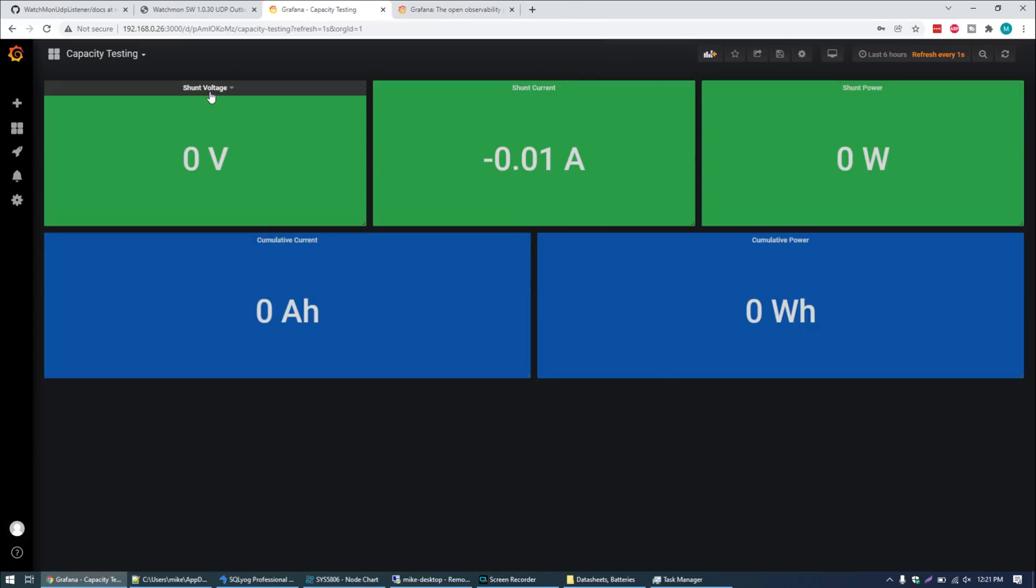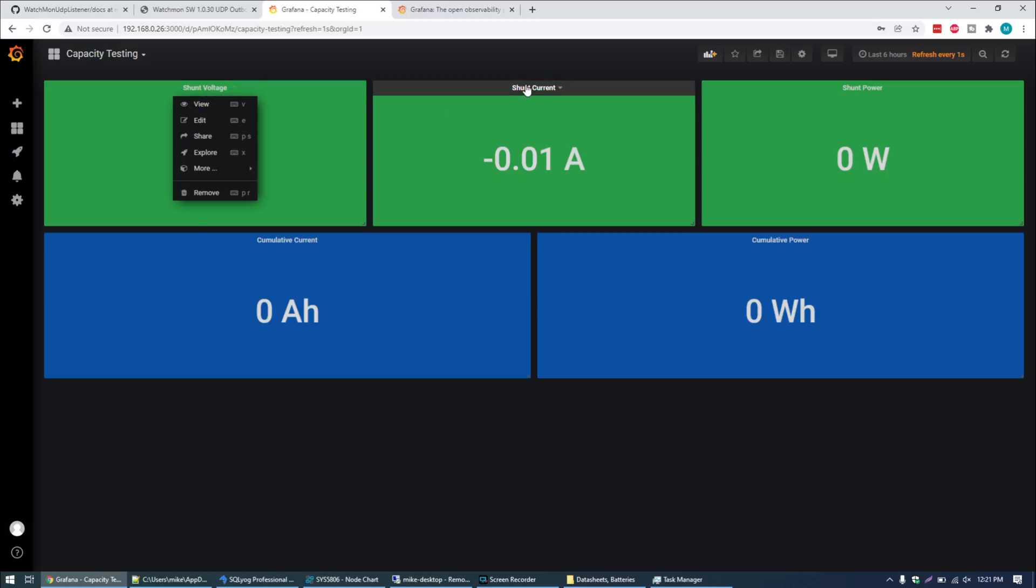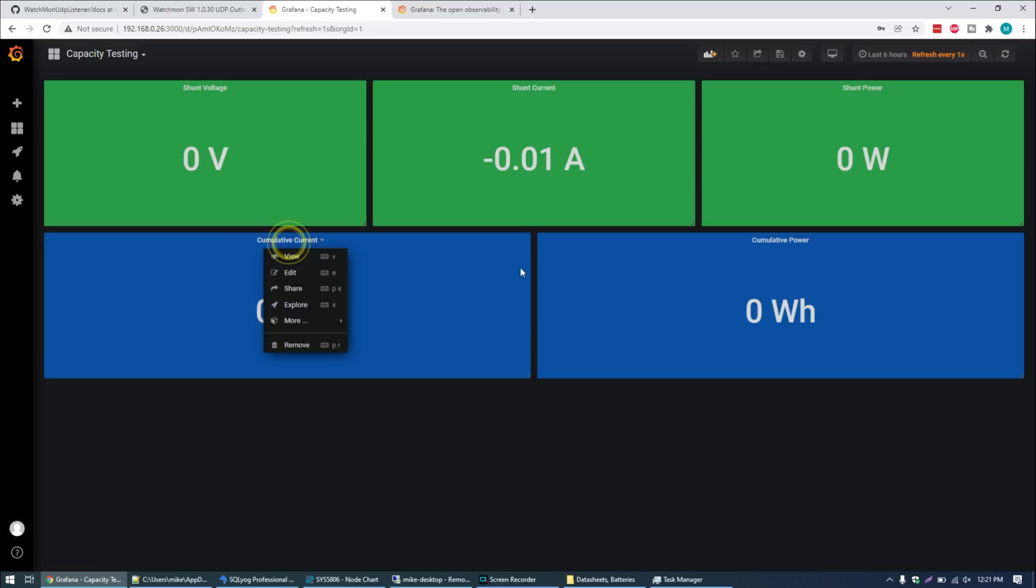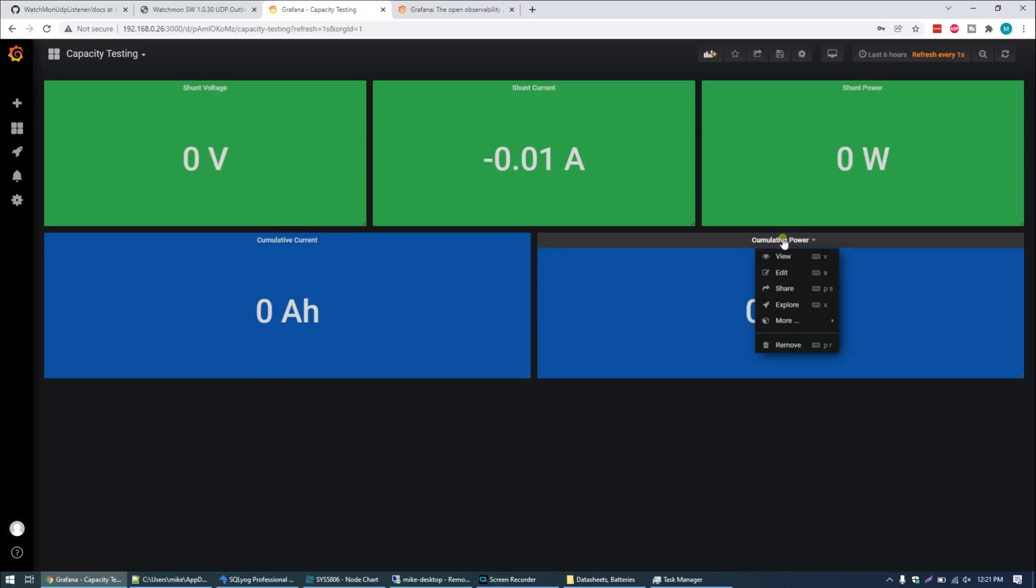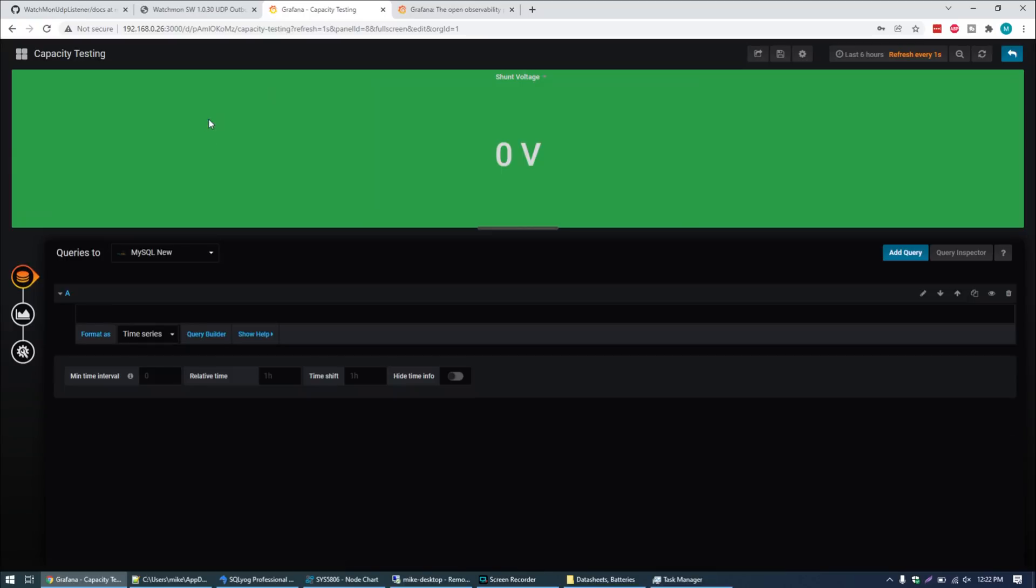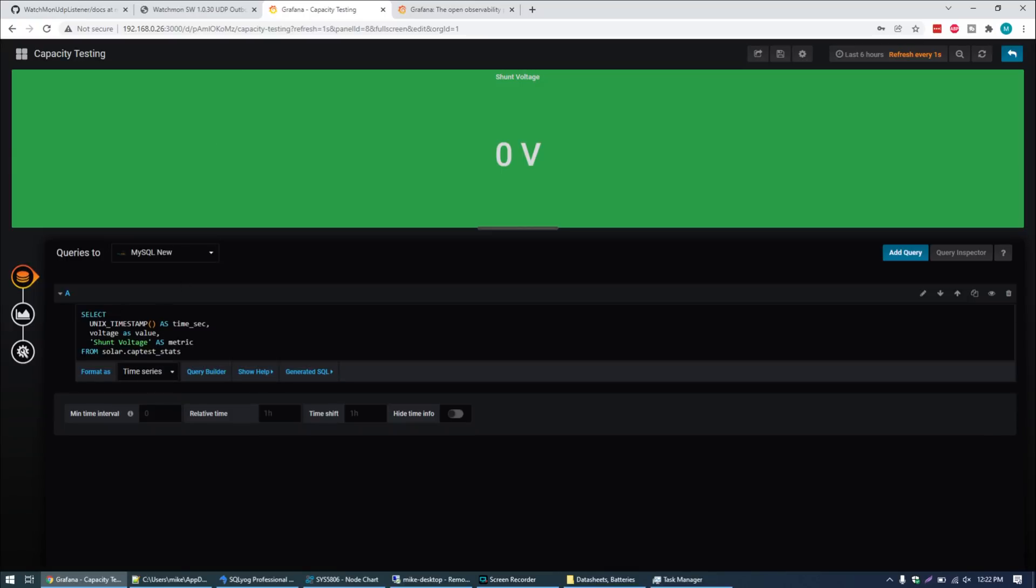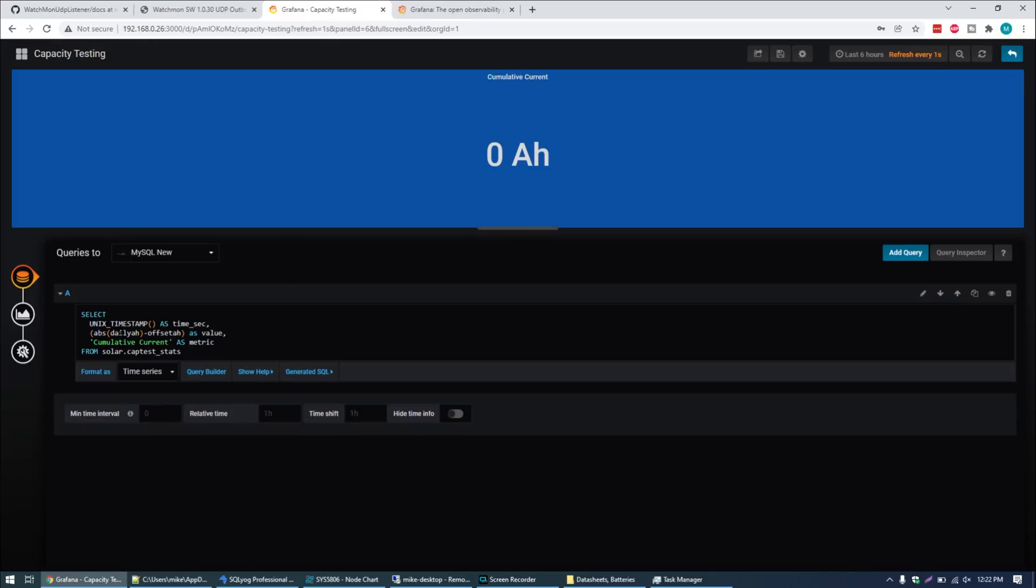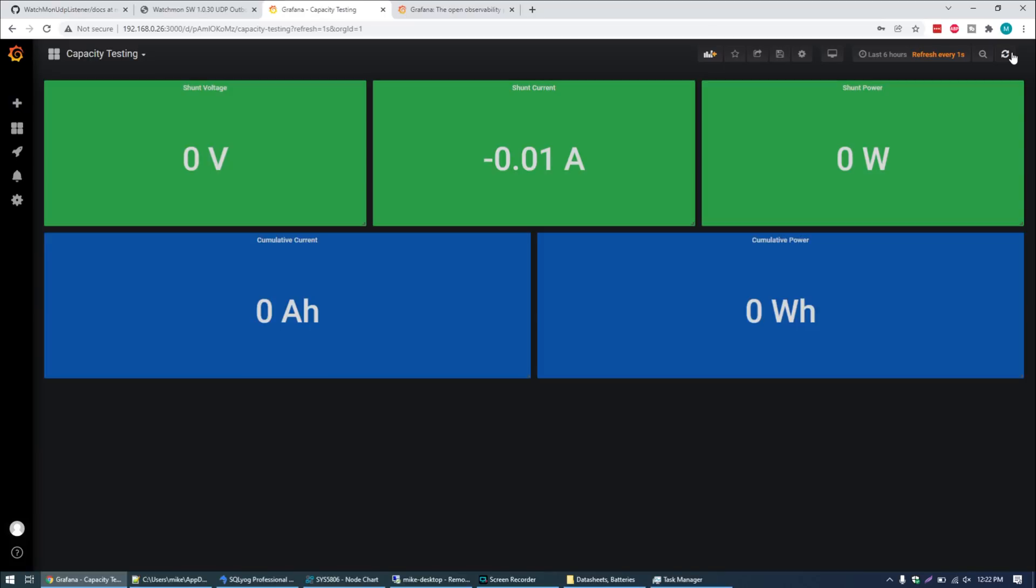It's a very fast and easy way to create dashboards. I have this installed on a separate server and here's the display you typically see on the tablet. We have the first column is shunt voltage. We have shunt current, shunt power, cumulative current and cumulative power. If I go into the display item for the shunt voltage you can see it's simply selecting the current timestamp, the current voltage column and then just the name of the data point from this cap test stats data. It's simply selecting those values and putting them on the screen. They're all the same, cumulative current's the same, cumulative power. It's selecting the daily amp hours and it's subtracting the offset that way we make sure we're zeroed out and it's only reading what was discharged during the test.